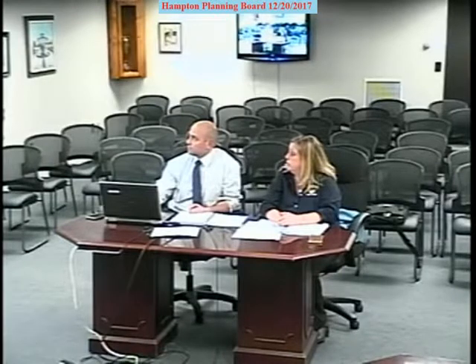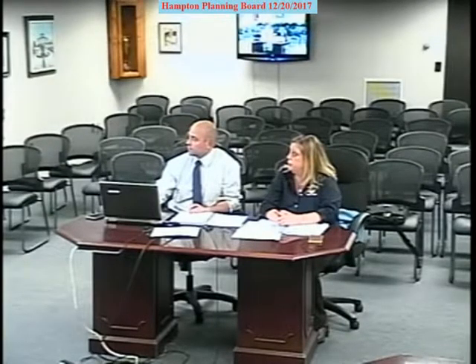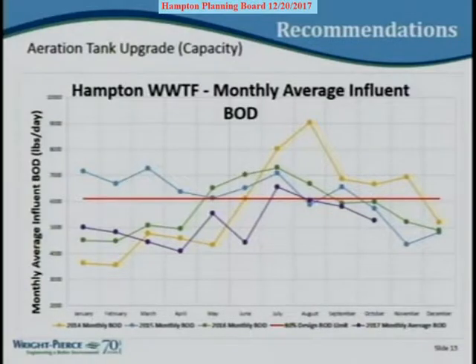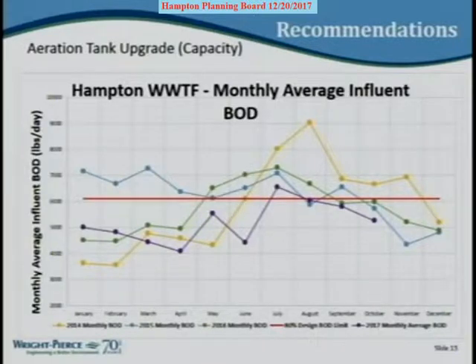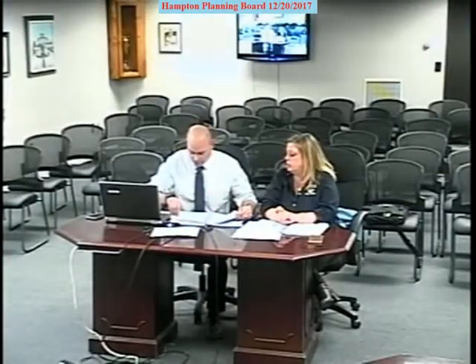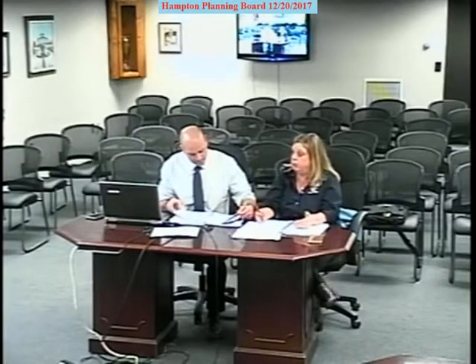The plant is at a certain load level today, and build-out will be at a higher level. The 80% threshold corresponds to roughly 7,600 pounds per day of BOD. There are months when it's been exceeded, but because the plant operators do excellent work and there's some safety factor built in, the plant has an exemplary compliance record for meeting effluent standards. The new aeration capacity will raise the treatment threshold above current levels - the specific new threshold number will be confirmed.